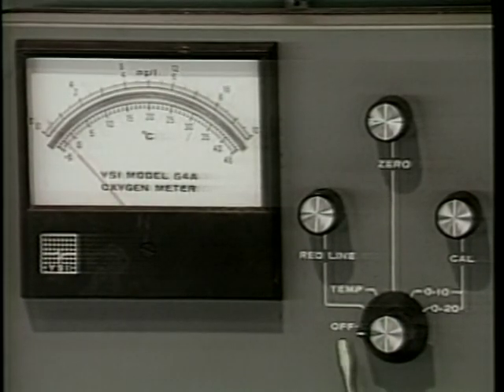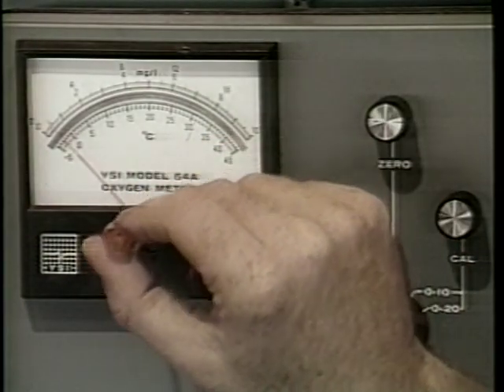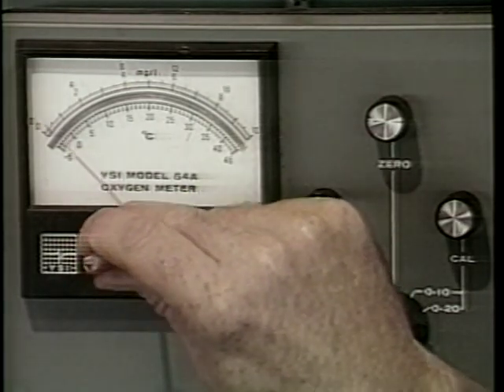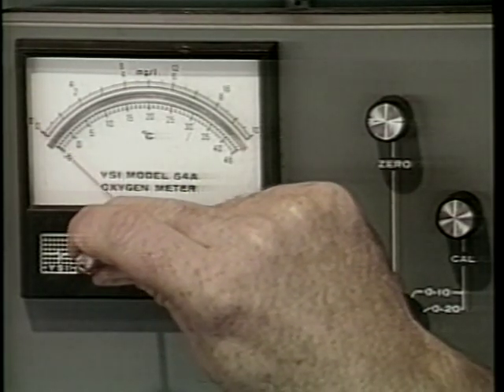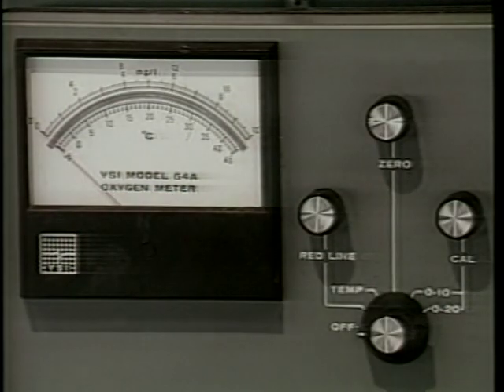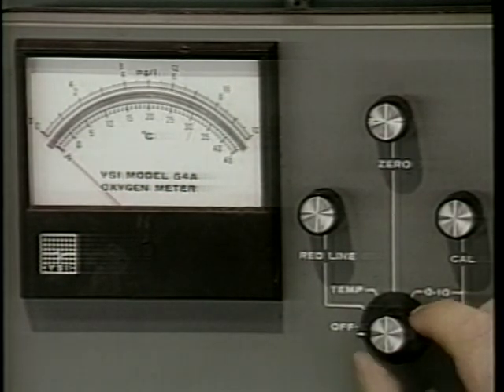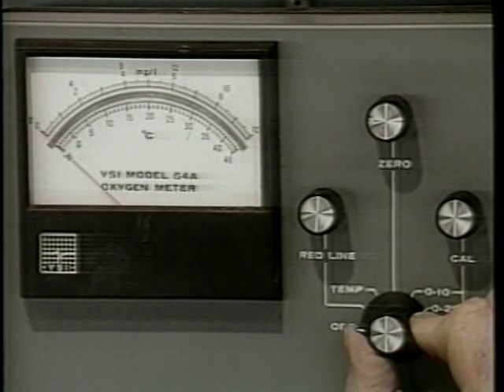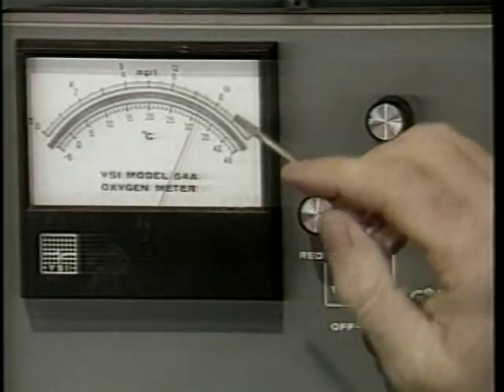First, switch the meter to the off position, and if necessary, adjust the needle to read zero by rotating the screw below the scale. If your meter has a red line knob, switch it to this position and adjust the knob so that the needle is directly over the red line.